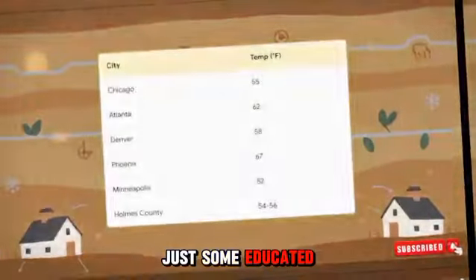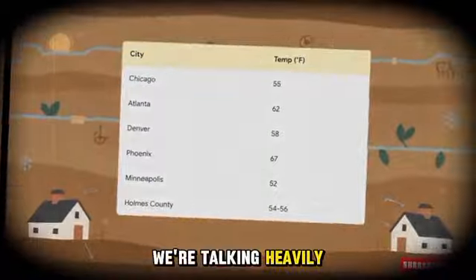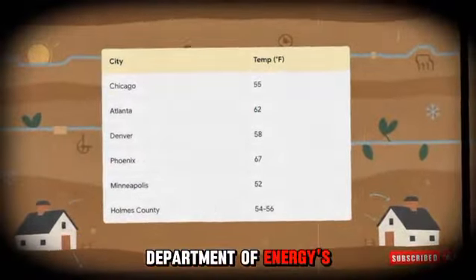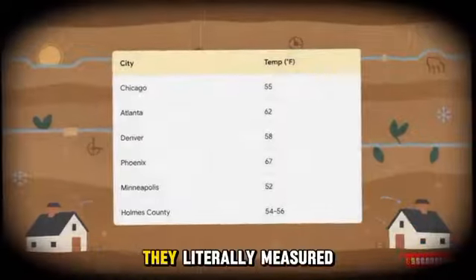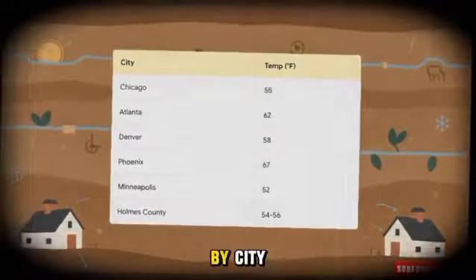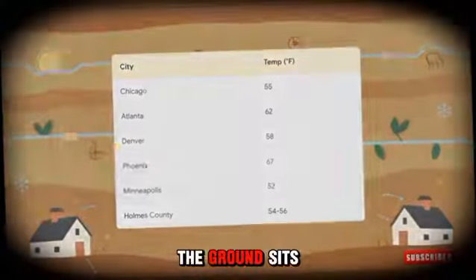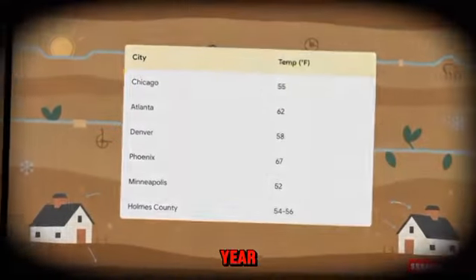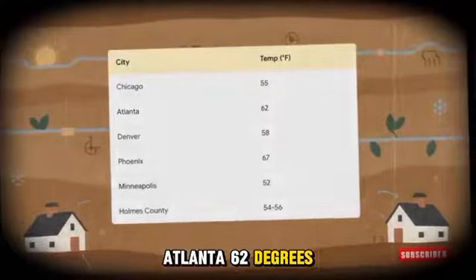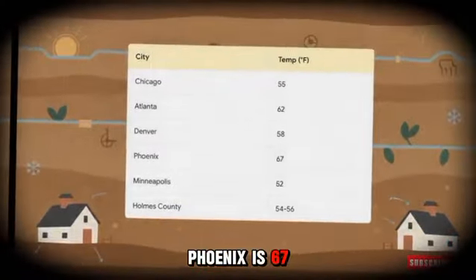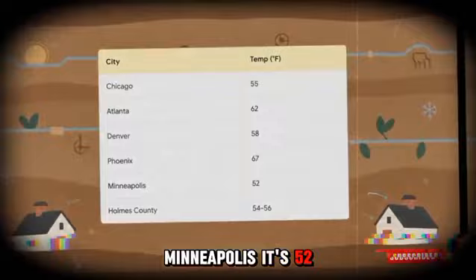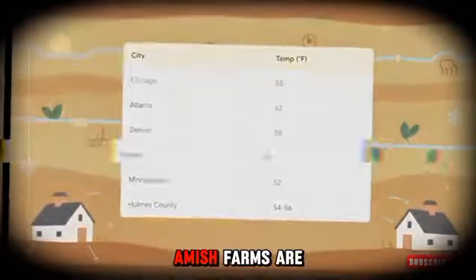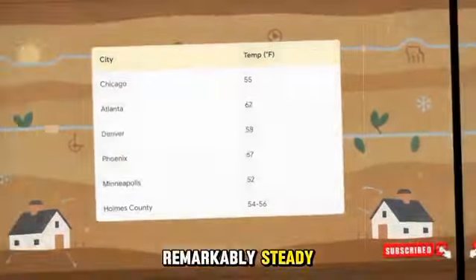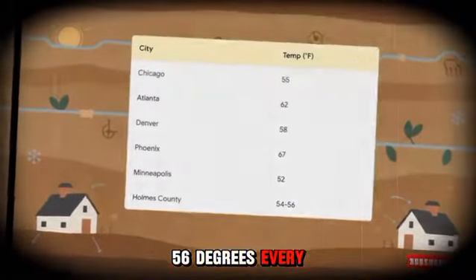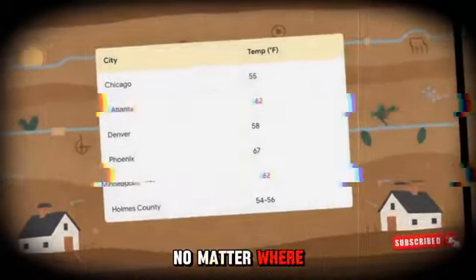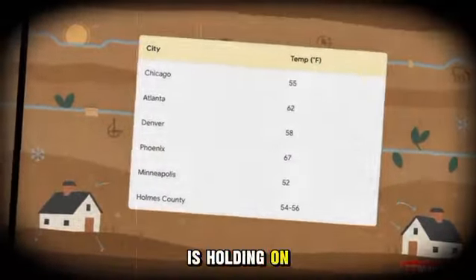And this isn't just some educated guess we're throwing around. We're talking heavily documented data straight from the Department of Energy's Oak Ridge National Laboratory. They literally measured soil temperatures city by city. Check this out. In Chicago, the ground sits at a stable 55 degrees all year. Atlanta, 62 degrees. Denver is 58, Phoenix is 67, and up in Minneapolis, it's 52. And right there in Holmes County, Ohio, where those Amish farms are, the soil holds remarkably steady between 54 and 56 degrees every single day of the year. It proves that no matter where you live, the earth right beneath your feet is holding on to a remarkably stable, cool temperature.